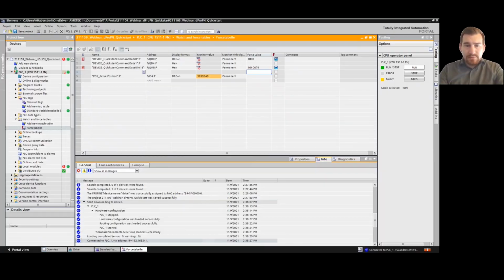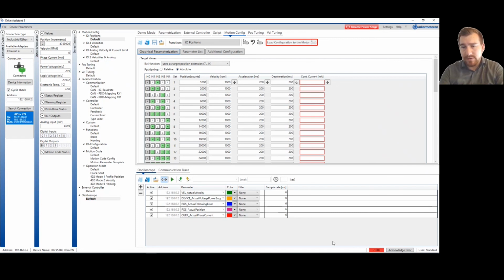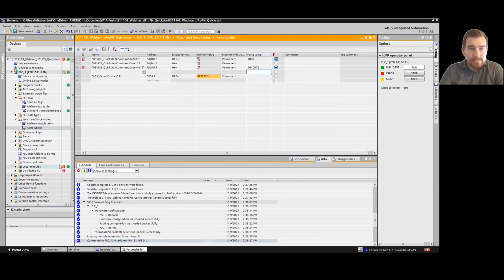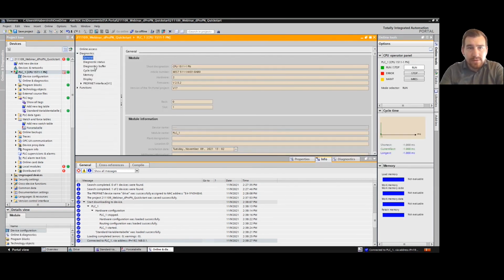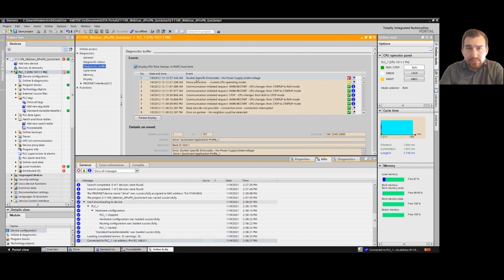Now let's see what happens if I switch off the power supply. Then we see here in the Drive Assistant that we have the error minus 1000, which is undervoltage. And in the TIA Portal, if we go into the diagnostics buffer, we see here the Dunkermotoren specific error code, hardware power supply undervoltage. If we had not enabled the diagnostics before, we wouldn't have this error message here.